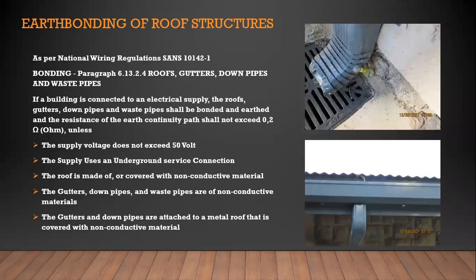We're looking at earthing and bonding of roof structures. You as plumber might change the gutters on a house or an installation building. If there's bonding present, I address that as well, how to put the bonding back once again, and what must be bonded and what's not allowed to be bonded. What does the electrical regulation stipulate on roof structures and downpipes, when to bond it and when not to bond it. I also address the downpipes, the waste pipes for the wash basins, bathtubs.